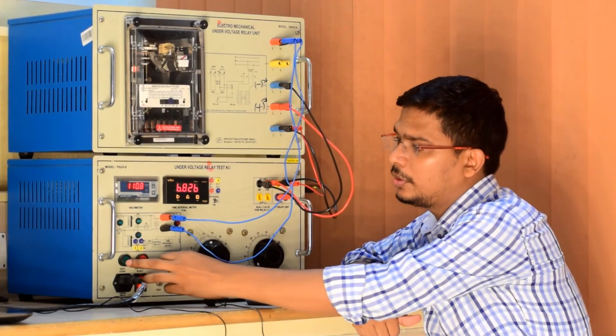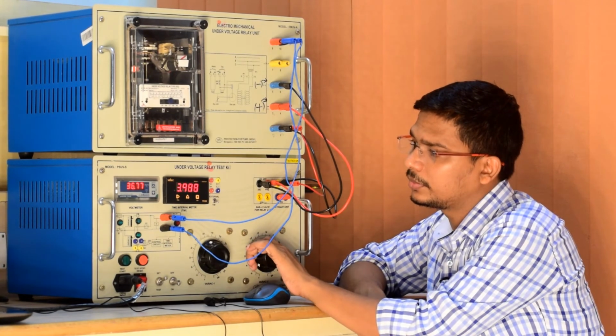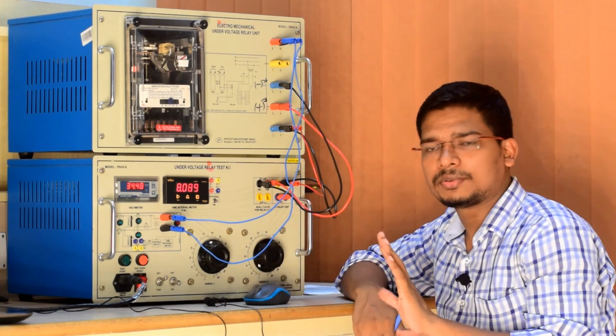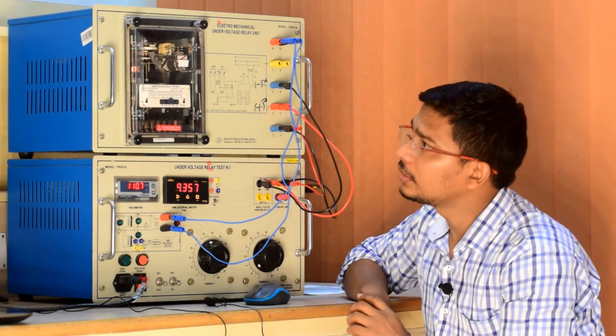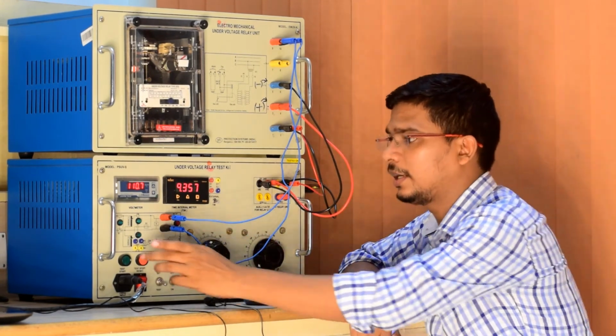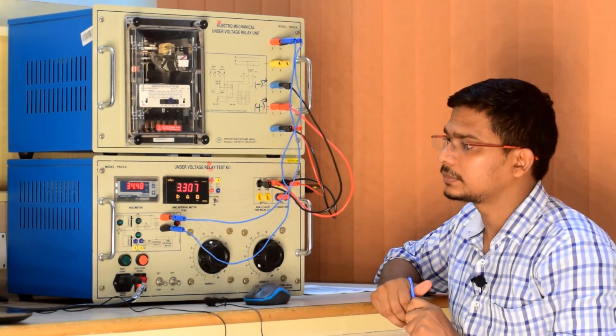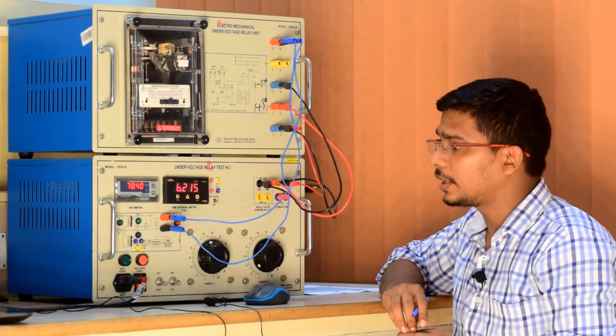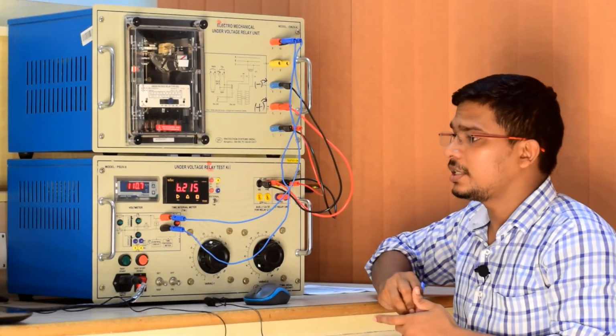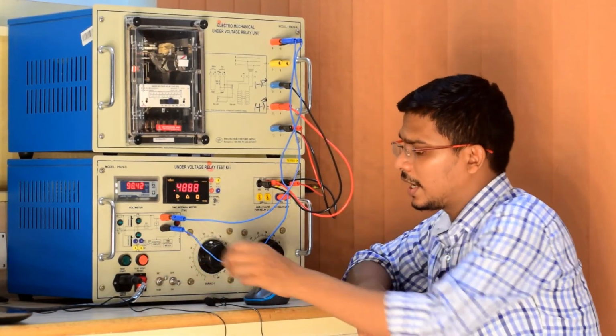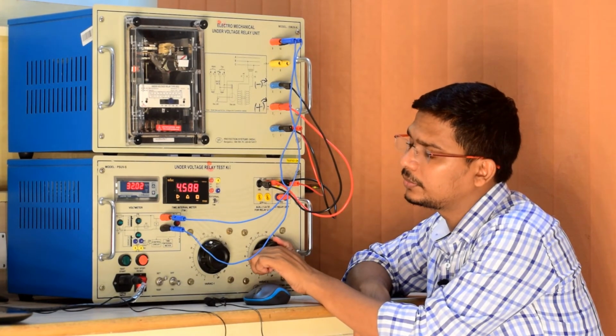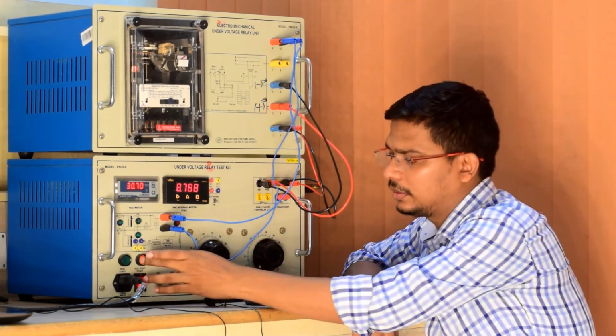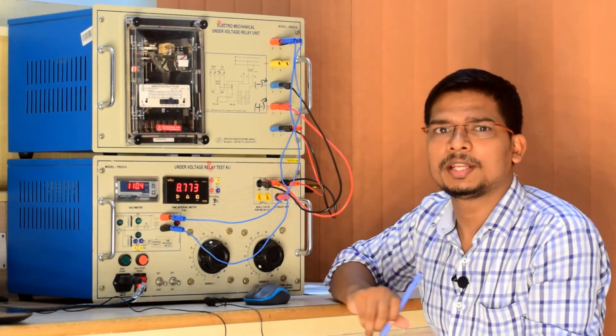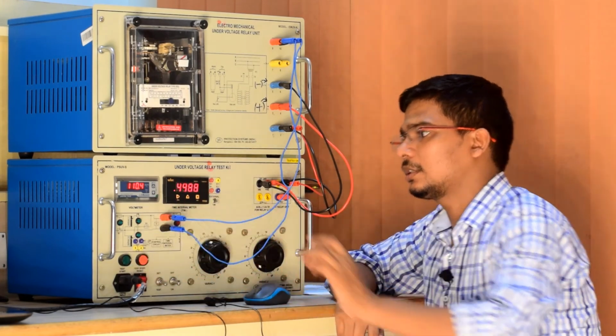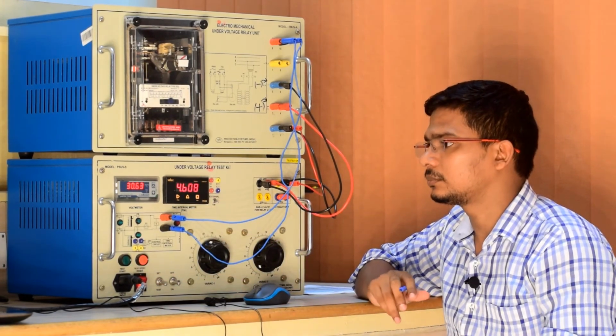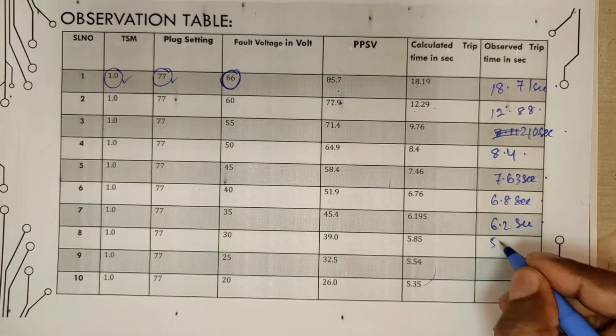Turn off, set mode, start it again, and the next voltage is 35 volt. Turn off, put to test mode, wait. You should see the relay come to a standstill. Yes, it came to standstill. Then start it again. Our expectation is 6.19, and we got 6.2 seconds. Next is 30 volt. Turn off, set, start. We have applied 30 volt. Turn off, test, wait. The disk is moving right now. Yes, it comes to standstill. Start it again. We got 5.9 seconds. Our expectation is 5.85 seconds.